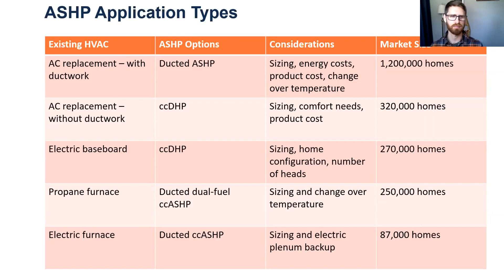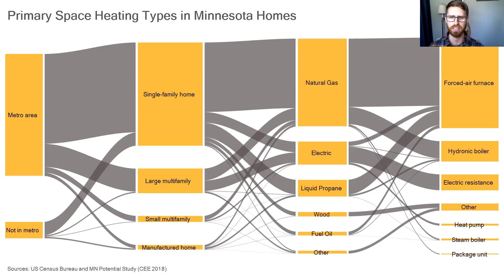Homes with air conditioners and natural gas furnaces encompass about 1.2 million homes, so that's the largest opportunity for heat pumps as AC replacements. For homes with natural gas heating to capture savings, we recommend considering a standard air source heat pump, at the very least sized to the cooling load, as an alternative to AC, to avoid folks buying air conditioners at this point. This hybrid approach with the existing furnace can also reduce short cycling, which is when a furnace turns on and off a lot because it may be oversized to the heating load in the shoulder seasons. So there are multiple value streams a heat pump can offer in the shoulder seasons, and there will be more on this topic released as part of the research project I mentioned earlier.